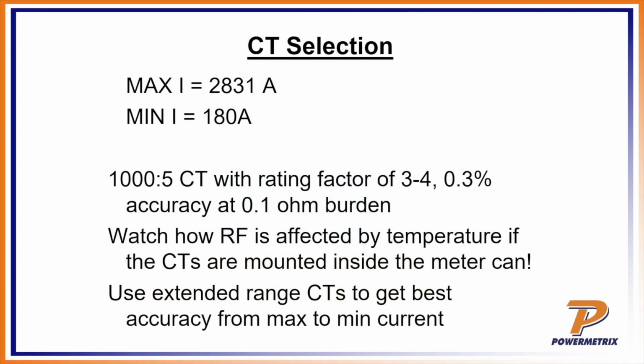So watch how the RF is affected by temperature. We just said that. If the CTs are mounted inside the meter can in the middle of the desert in Arizona, I used to work jobs out there many years ago, and we literally put a giant thermometer out on a big asphalt parking lot out there in California. 135 degrees. Yeah, we melted the bottom of some of our boots, it got too hot. So it can get hot, and it will definitely affect the CT, that rating factor, okay?